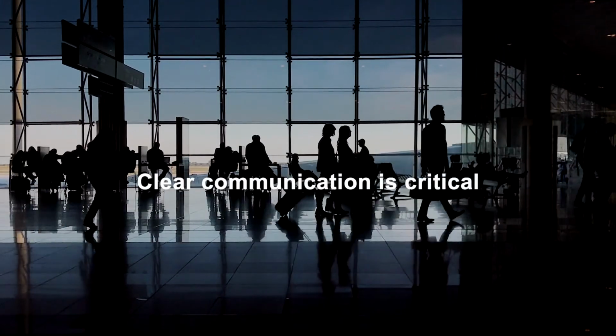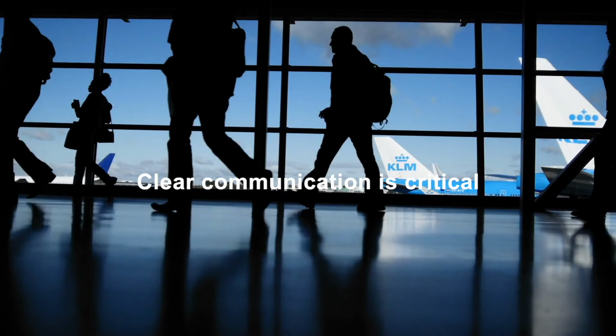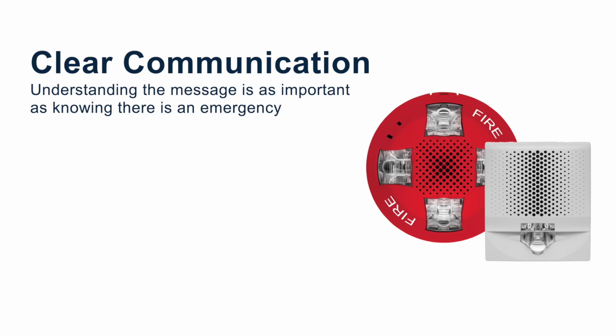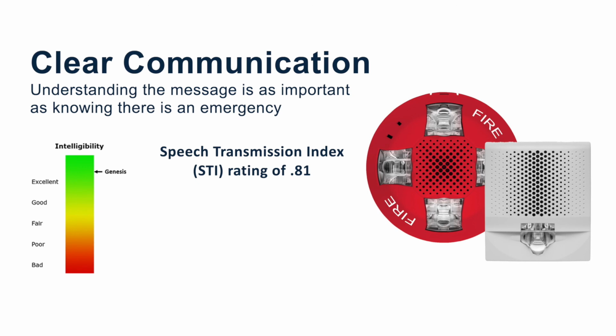Clear communication is critical in fire applications. Occupants need to know there is a fire event, but understanding the message is as important as knowing there is an emergency. The Genesis LED series speaker strobes are rated to a 0.81 STI rating, and anything above 0.76 is considered excellent. STI stands for Speech Transmission Index and measures how understandable spoken language is over an audio application. With an STI of 0.81, Genesis LED ensures occupants can hear evacuation messages and react appropriately in an emergency.